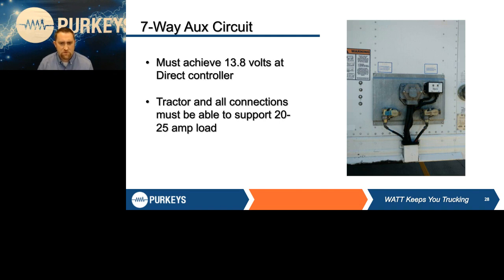So again, that circuit has to support that 20 to 25 amp load. What do you have with a 7-way circuit? You have much smaller wire. Typically, it's 8 gauge, 10 gauge wire. You have a lot more connection points between the truck. It's got to go through a control panel, through all the connections at the battery, and then up to the receptacle, through the 7-way cord, and to our controller. So there's a lot of connection points that can choke off that voltage and that current flow. And by the time it gets to our controller, it may be too low.